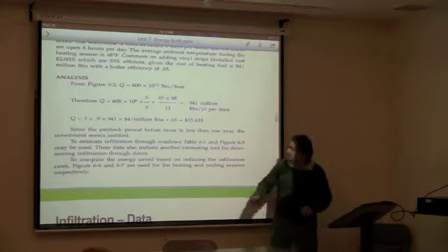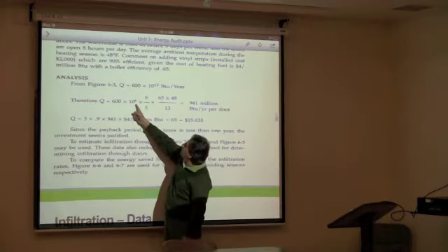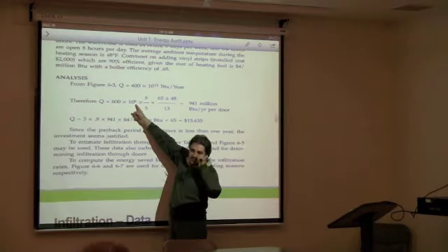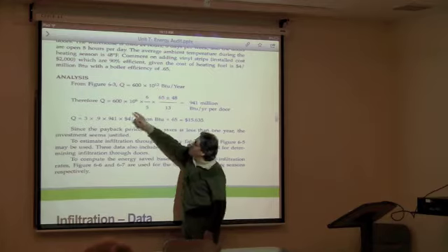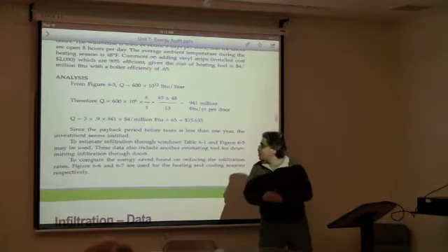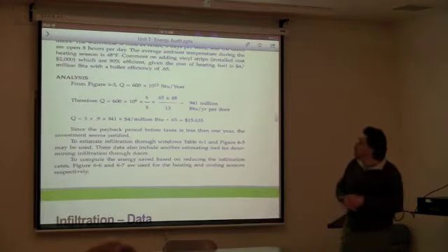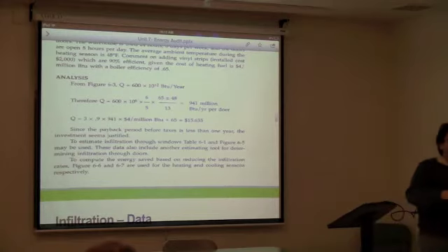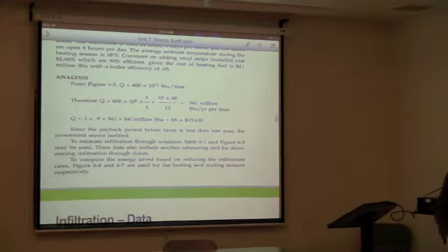Yeah, here it is 6, not 12. And that's why here it is 6. So I think it is a typo here. So 600 million BTU per year I'm losing because of these 6 open doors that I have, and each of them is 10 by 10.